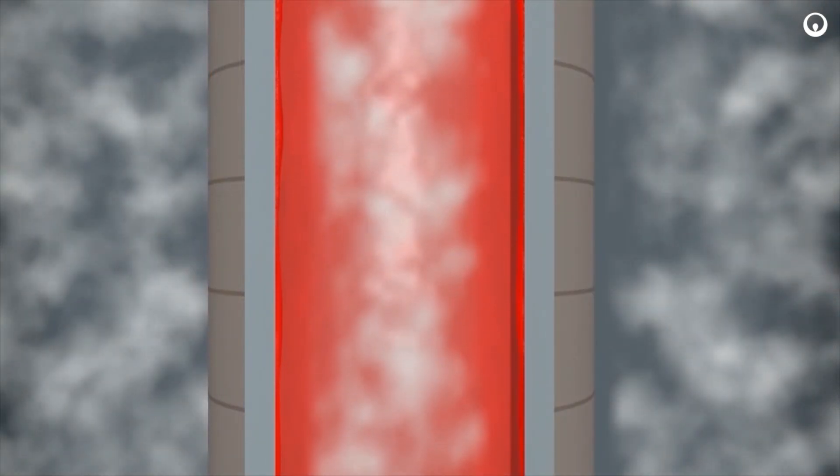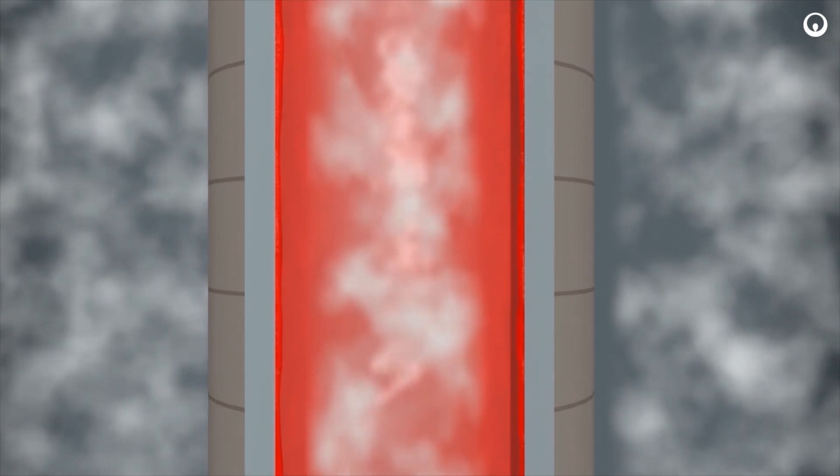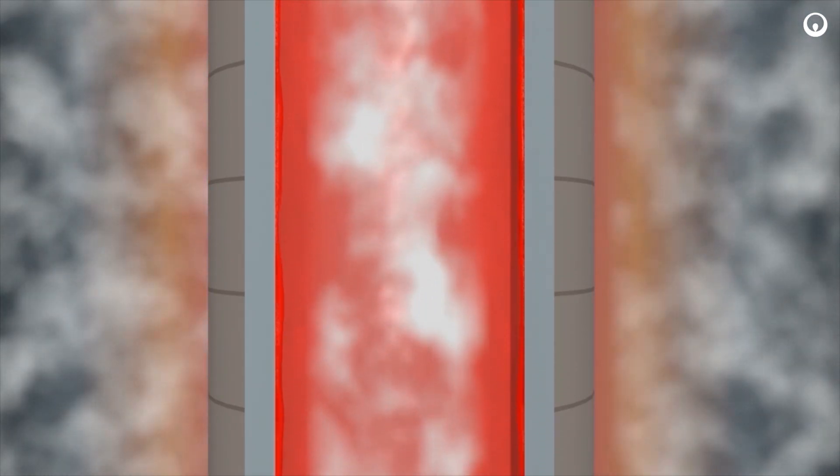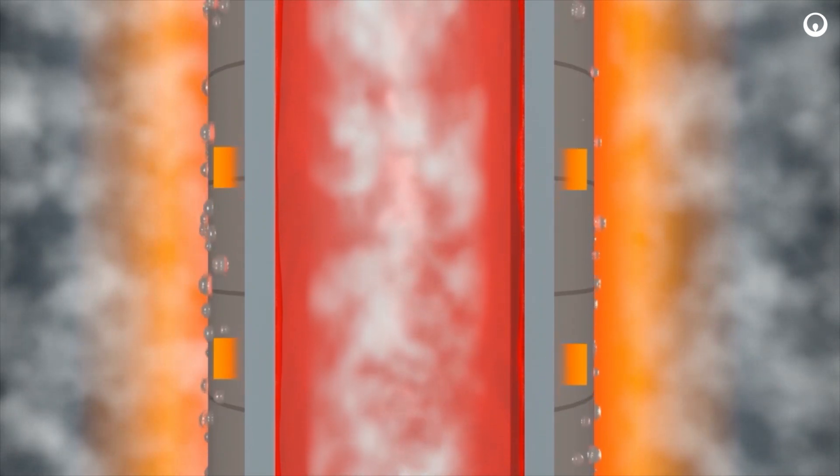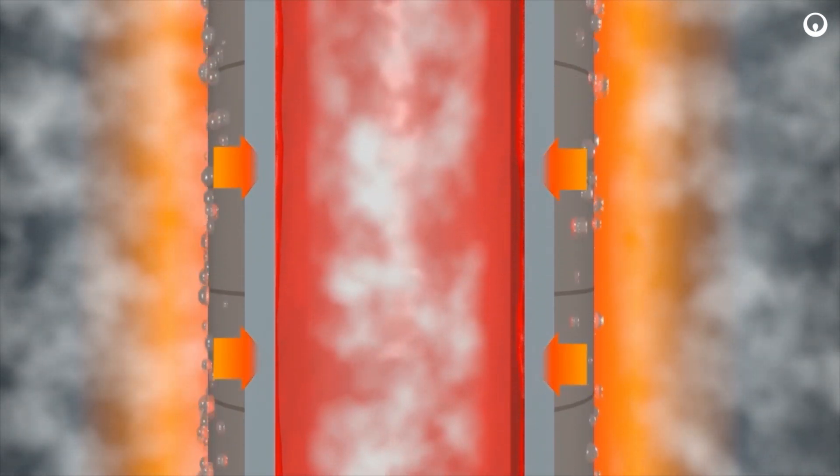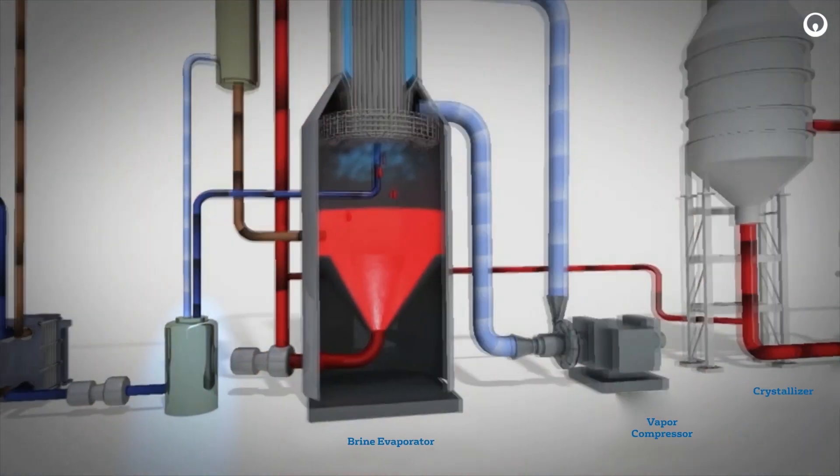The compressed vapor flows to the shell side of the heat transfer tubes of the brine evaporator. The vapor condenses on the outside of the vertical tubes. The condensed vapor flows down the outside of the heat transfer tubes and is recovered as a distillate.